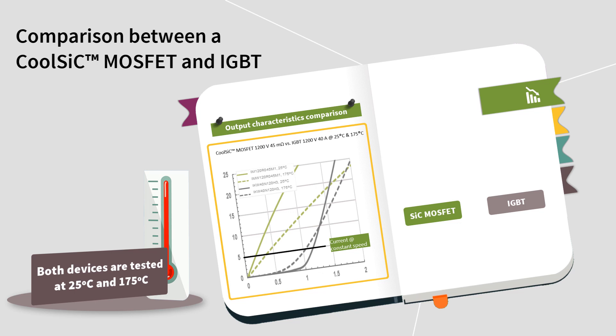By looking at the graphic, we can say that during constant speed mode, which is more than 90% of the time, the semiconductors work at a very low current. While at a low current, the silicon carbide MOSFET has a much lower power loss when compared to an IGBT.